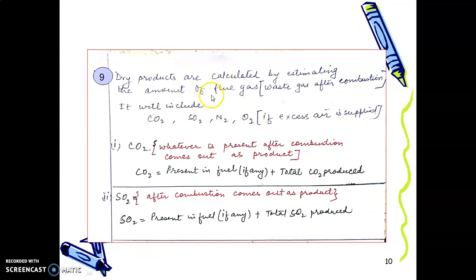How can oxygen be calculated? The actual air supplied minus air required, into 21 by 100. That is, excess air into 21 by 100. Why is it done so? Actual air supplied means if you are supplying minimum air plus excess air for a perfect combustion, then you will have a value of actual air supplied. Air required is the minimum air required.